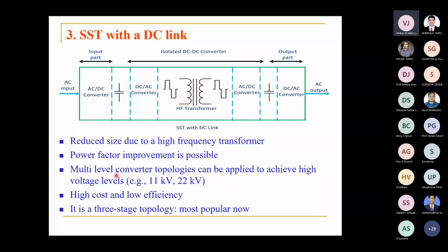Multi-level converter systems can be adapted for this application to meet high voltage requirements with limited rating semiconductor devices. The key demerits are higher cost, and since we are adding a number of power converters, comparatively lower efficiency.